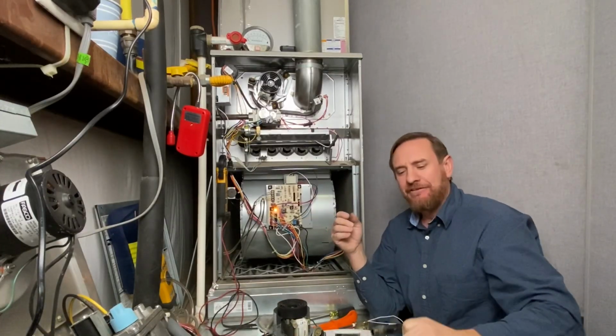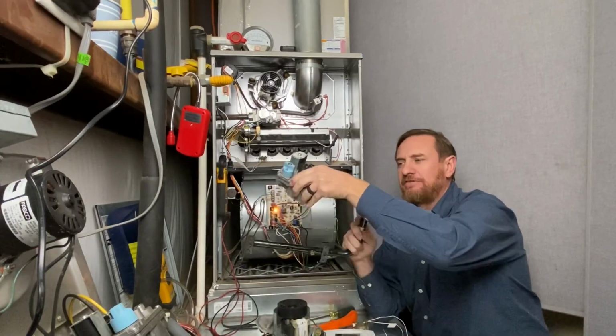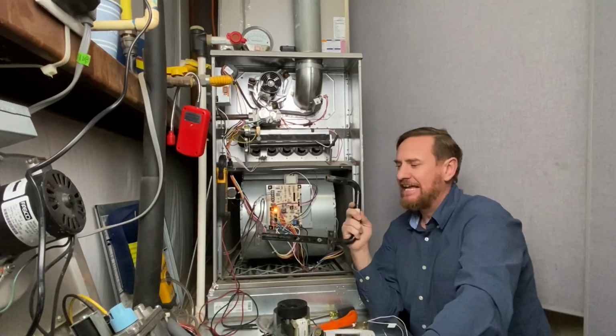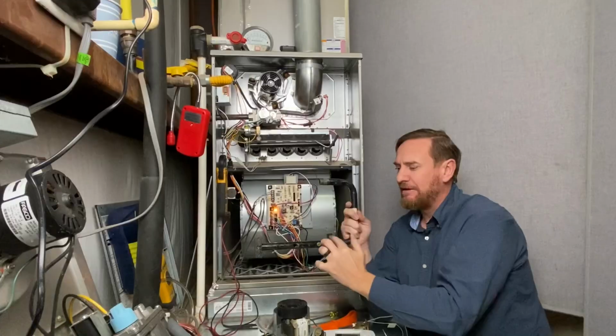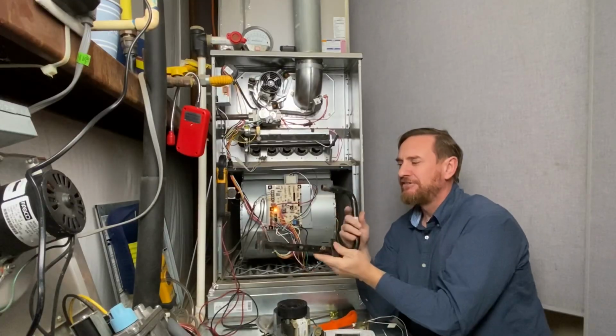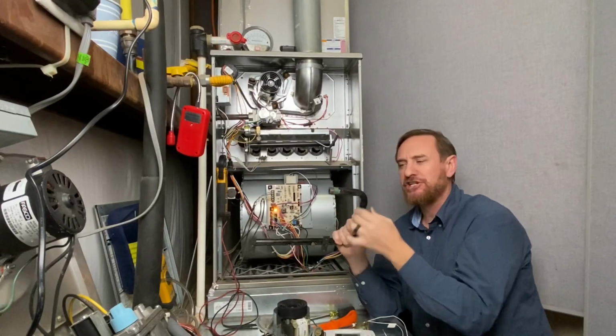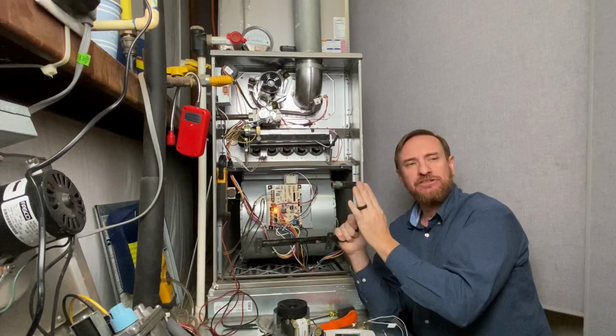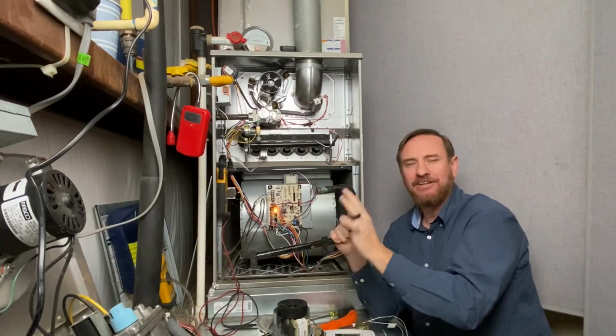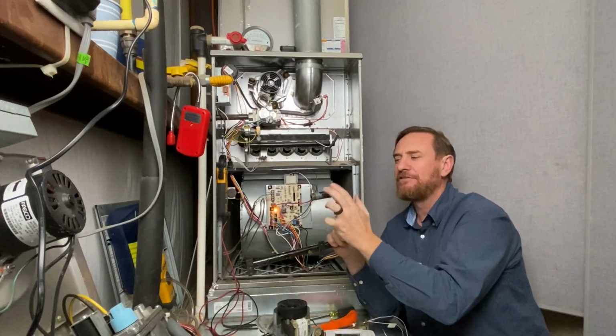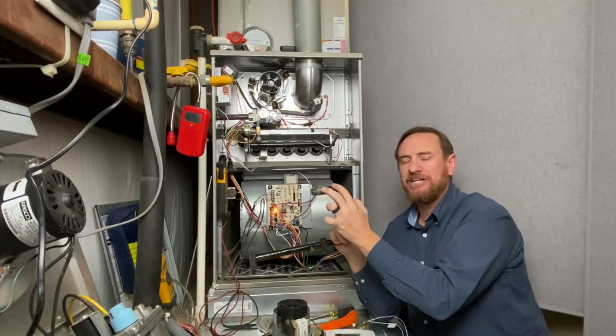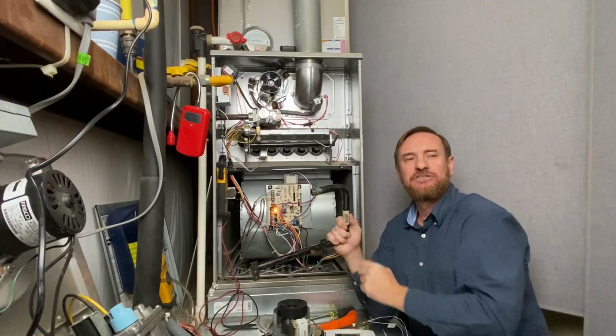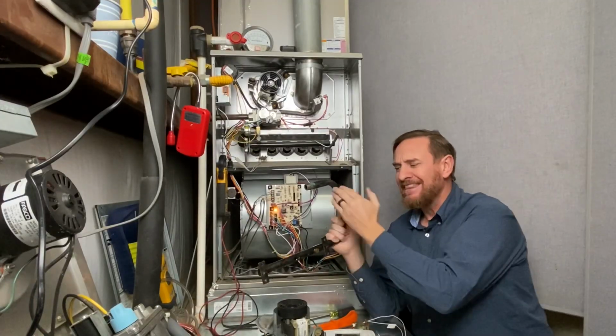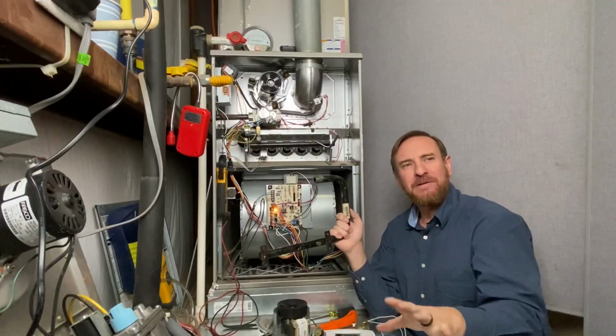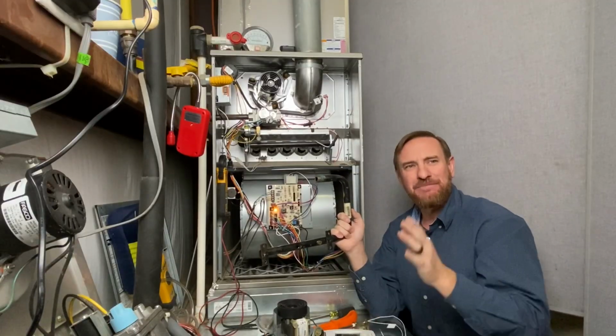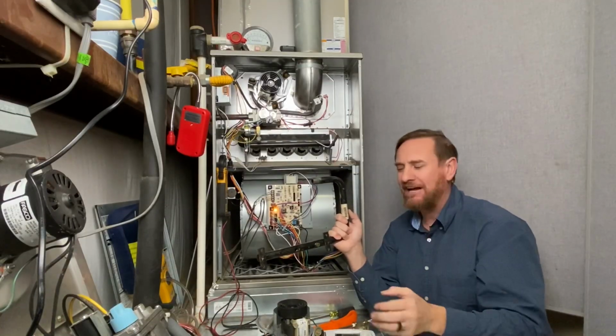It's called the manifold. So leaving the combination gas valve, we have the manifold. It takes the gas from this one valve and separates it to multiple points. So this is the manifold. It's also called manifold pressure. You're going to need to read the manufacturer's instructions, but typically, this is not set in stone, but typically you have 3.5 inches of water column for natural gas and 11 inches of water column for propane. That's in your manifold. Don't go by those numbers. Check with your manufacturer and make sure that's what they want for that altitude.